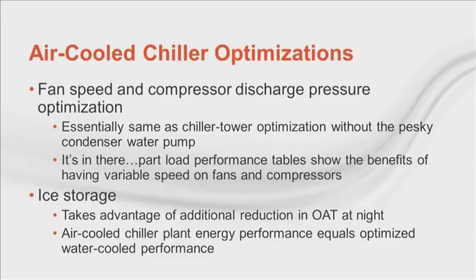In our 2009 broadcast, we showed how air-cooled performance changes proportionately more than water-cooled performance, because there is more reduction in the outdoor air dry bulb temperature than in the wet bulb temperature. So we see a bigger benefit from running the air-cooled chiller at night than during the day. If your building doesn't have load at night, this means storing the energy at night to deploy during the peak times of the day.